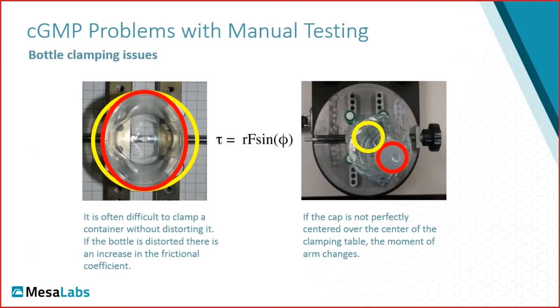And on the next slides, I want to go through issues with manual testing, and even if you do manual testing, you should pay attention to these issues. Or if you're ready to move to automated testing, these are the reasons why you should, or what is going to be better when you move to automated testing. One of them is that it's often difficult to clamp a container without distorting it, or different operators clamp the bottle to different pressures, and depending on the bottle design, or in this case a jar, it will distort differently. Now, when you try to apply a closure or measure removal torque on a closure that's distorted like that, it's going to have a different value than if another operator does it properly and the opening is not distorted.